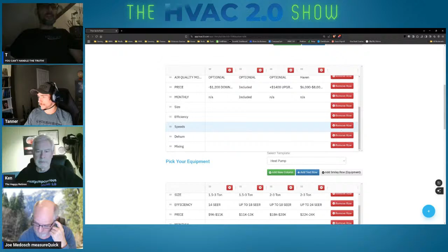And this is where the better equipment comes in, because they can set the fan to continuous and set the speed, and then they get continuous mixing. And if they add in fresh air, that really helps. Most of the time that solves the CO2 problem in the bedroom. Or if they have odors, or high occupancy - a lot of it comes down to the use case of the occupant.